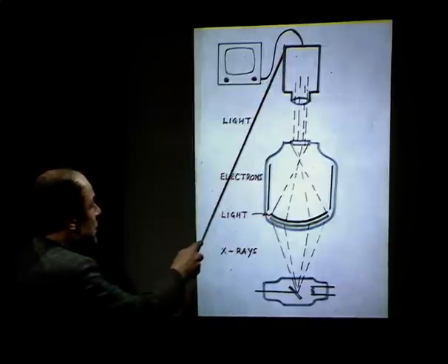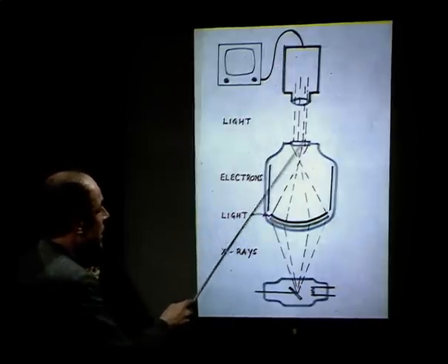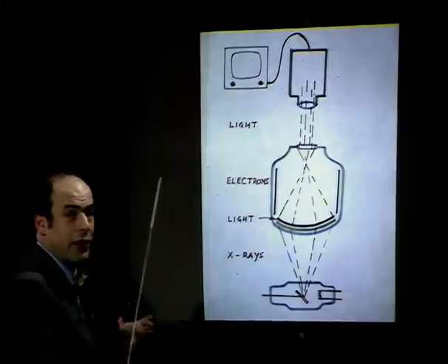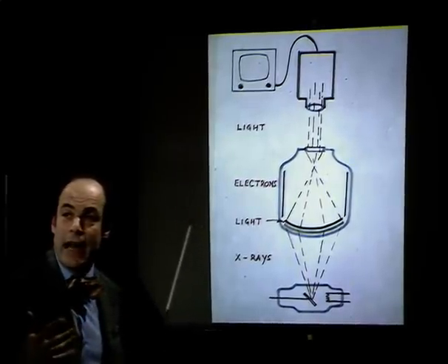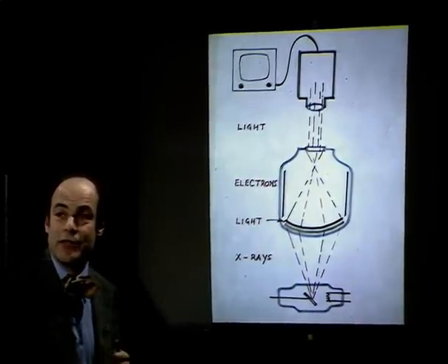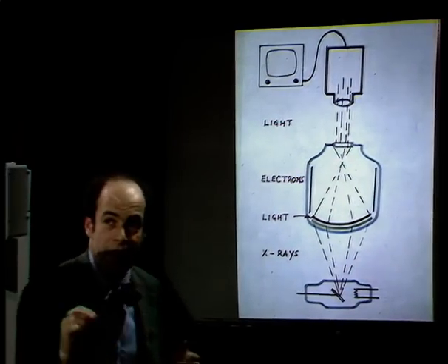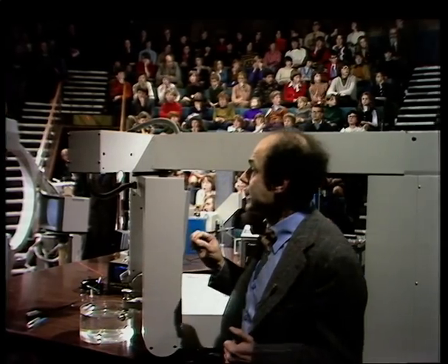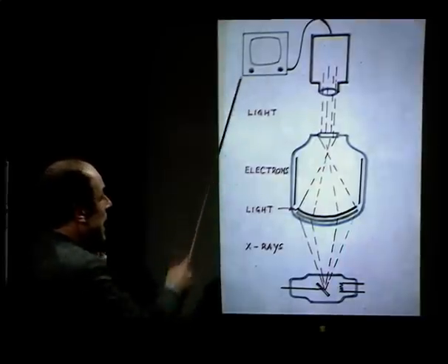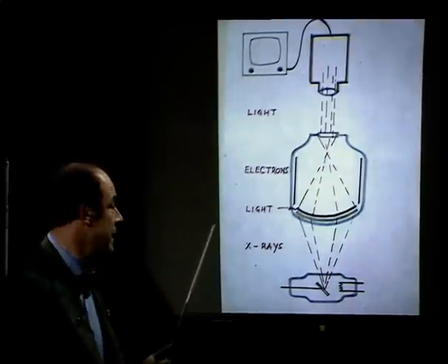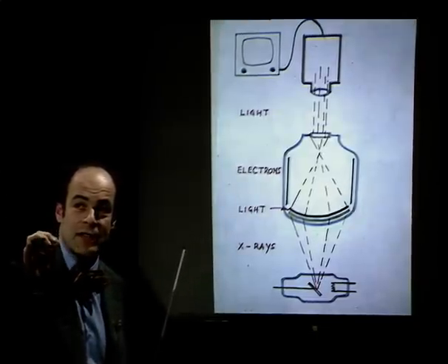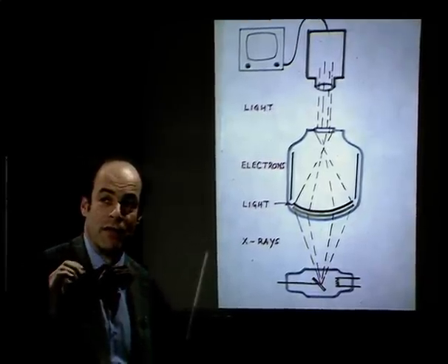We can then use a television camera to look at this tiny picture here, and once having got it on a television camera, we can make the picture appear on an ordinary television monitor, which can be viewed in broad daylight, or certainly in good illumination. So we've achieved three very important factors here. The first one is that we've taken away the need to sit in the dark for fluoroscopy, because we can now look at the image in comfort in a lit room. Secondly, the actual resolution which one can get on the picture, the fineness of the detail which one can see on the picture, has been improved by this device.